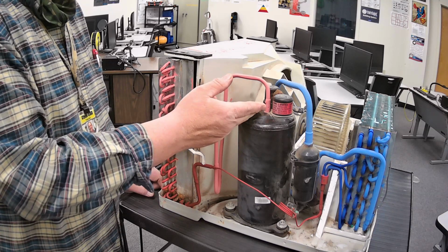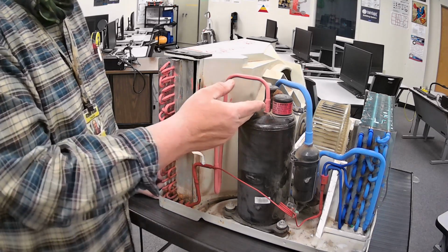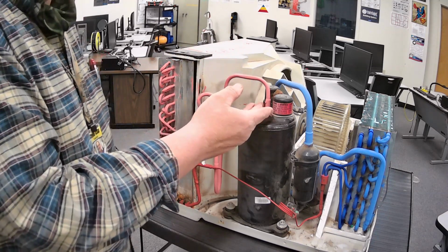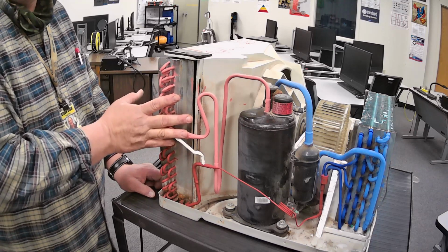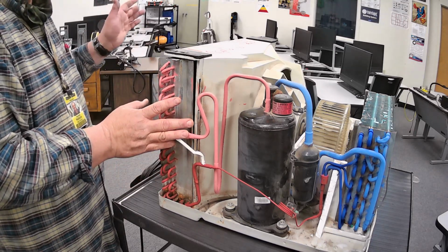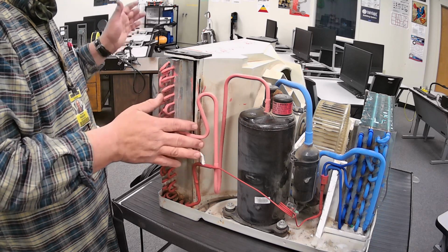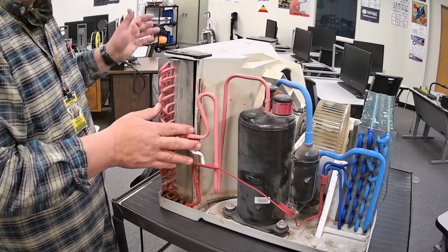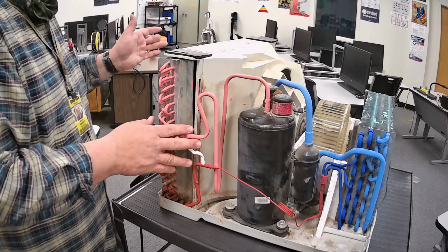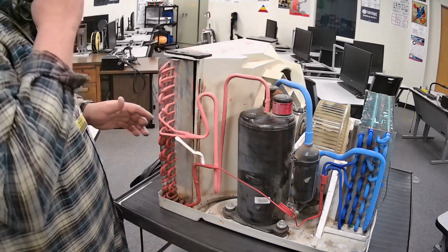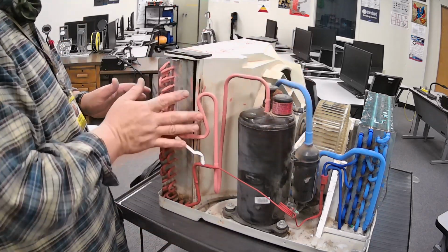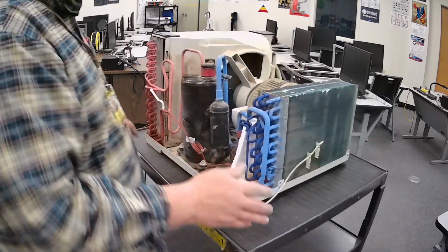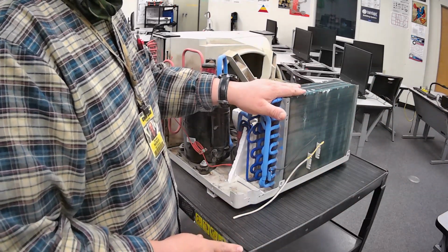So let's say on a very hot day, it's 100 degrees. That refrigerant is still 210 degrees. So how does heat travel? From a high to low. So this is a high, and where's the low? The outside temperature. So the 210 degrees is trying to go to the 100-degree temperature outside, which normally around Abilene is about 95. So it's attaching to the 95-degree temperature. So we're going from a high to a low on the outside, and then we're going from a high to a low on the inside on the evaporator.